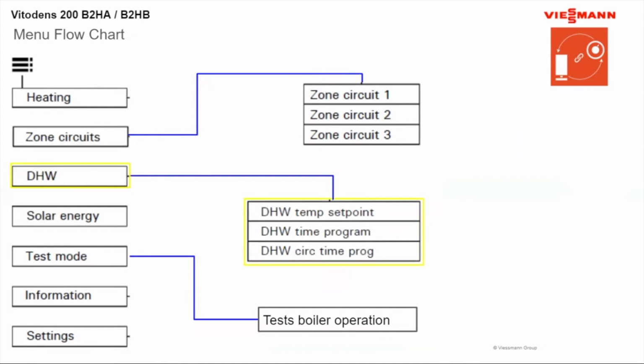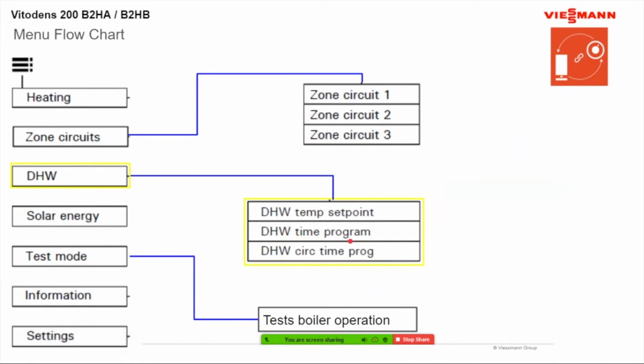That same menu button at the very bottom with the controls, if you want to change your domestic set point temperature, or here's where you would do your DHW time program or your DHW recirculation time program. Remember, if you click on your DHW time program, it will say automatic and individual. If you are doing a heating time program and you leave it in automatic, it will automatically follow the time program that you have for your heating. If you want to just do an individual time program just for your domestic, you can do that. You would click individual, the time program would come up, and then you just set the times you want it to come on and off throughout the day.